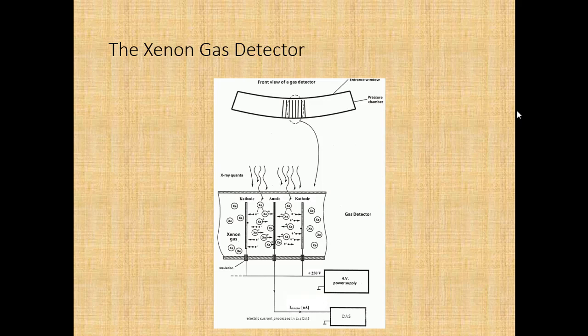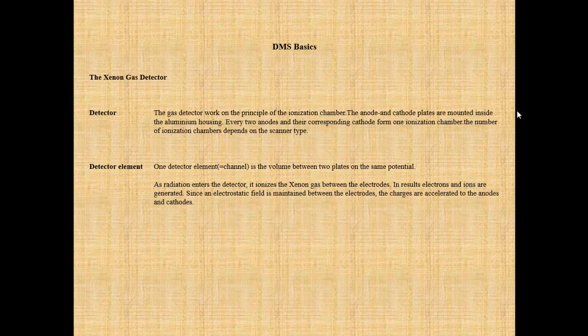The xenon gas detector works on the principle of the ionization chamber. The anode and cathode plates are mounted inside an aluminium housing; every two anodes and their corresponding cathode form one ionization chamber. The number of ionization chambers depends on the scanner type. One detector element equals one channel, which is the volume between two plates at the same potential. As radiation enters the detector, it ionizes the xenon gas, generating electrons and ions that are accelerated to the anodes and cathodes by the electrostatic field.